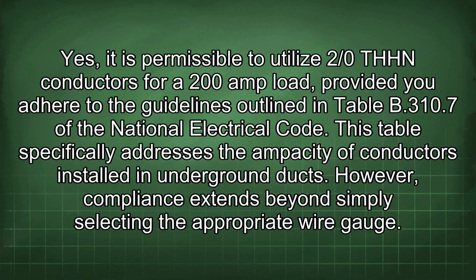Yes, it is permissible to utilize 2/0 THHN conductors for a 200 amp load, provided you adhere to the guidelines outlined in Table B.310.7 of the National Electrical Code. This table specifically addresses the ampacity of conductors installed in underground ducts. However, compliance extends beyond simply selecting the appropriate wire gauge.